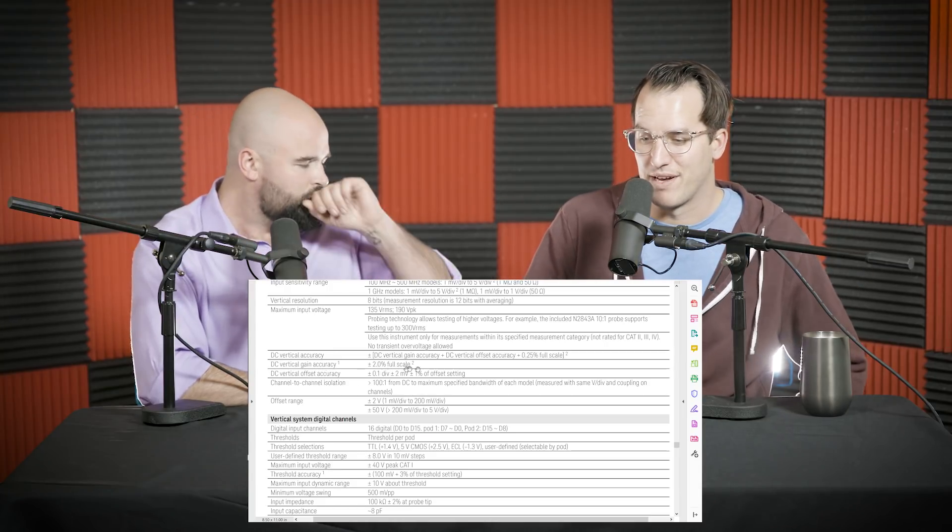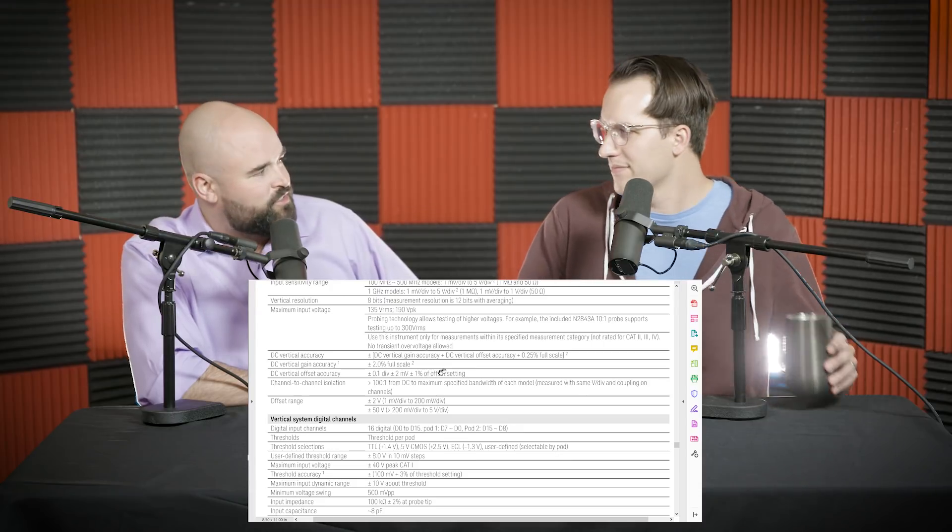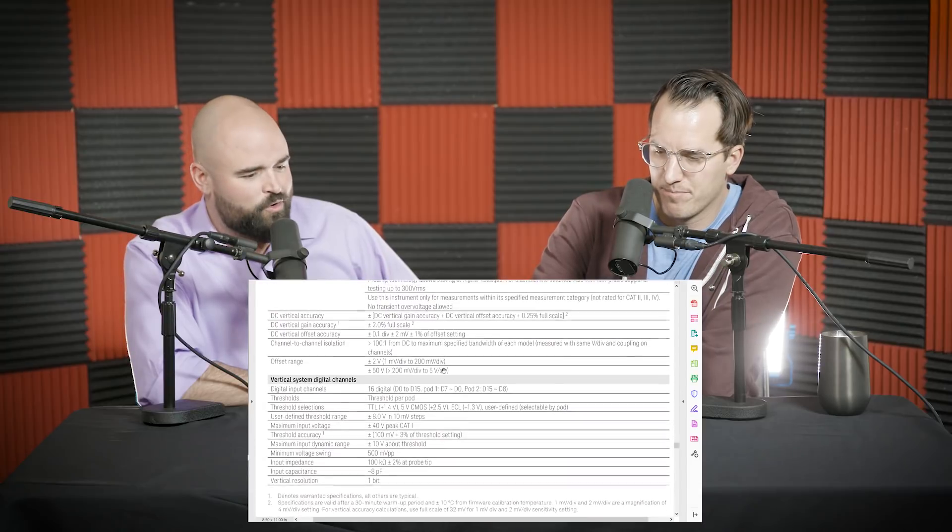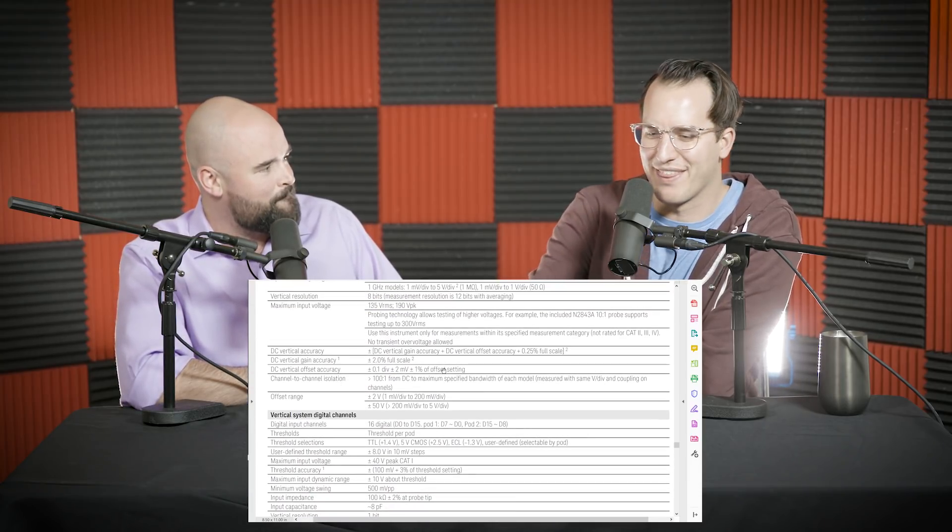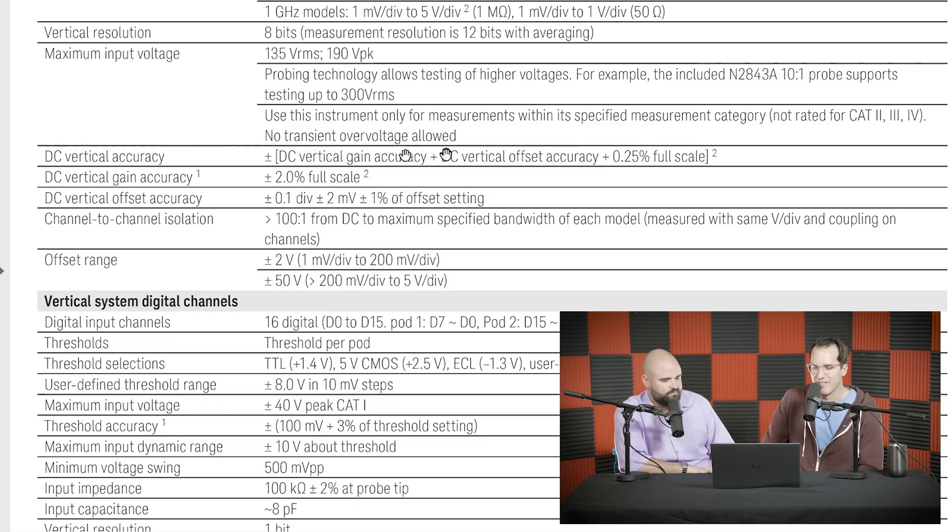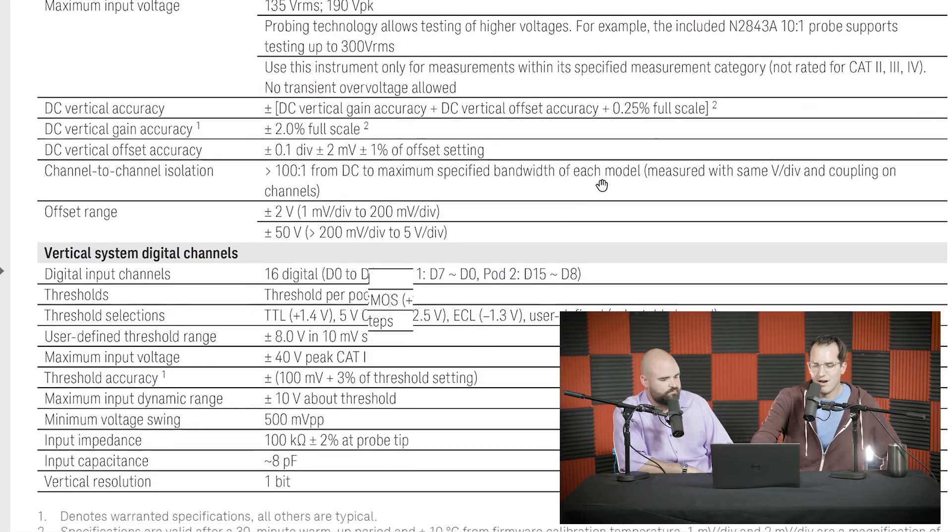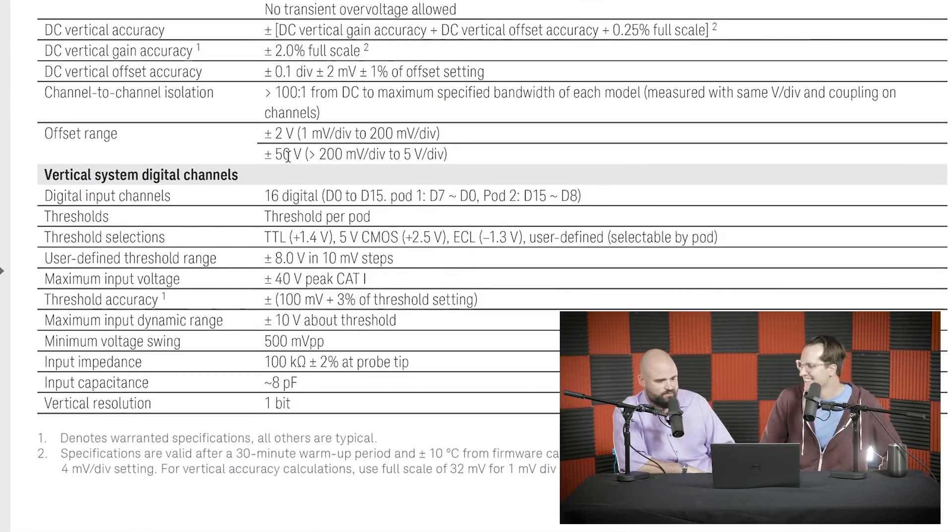So that's what everyone specifies is DC Vertical Gain Accuracy. And then there's additional uncertainties on top of that, which is offset. So as you start to add offset, plus or minus the division, plus millivolts, plus one percent of the offset setting. Somebody really bored should go do a history lesson of data sheets because I found that a lot of our data sheets in the oscilloscope industry from all vendors are organized pretty much the same. We all have the same warranted specifications. I wonder when did DC Vertical Gain Accuracy first get spec'd, and how long was it until everyone else had to follow suit?